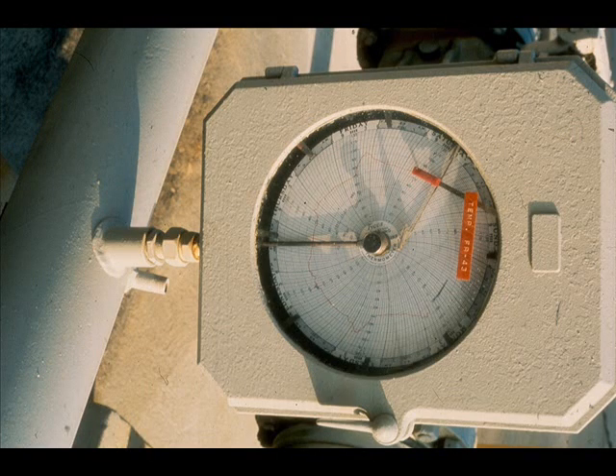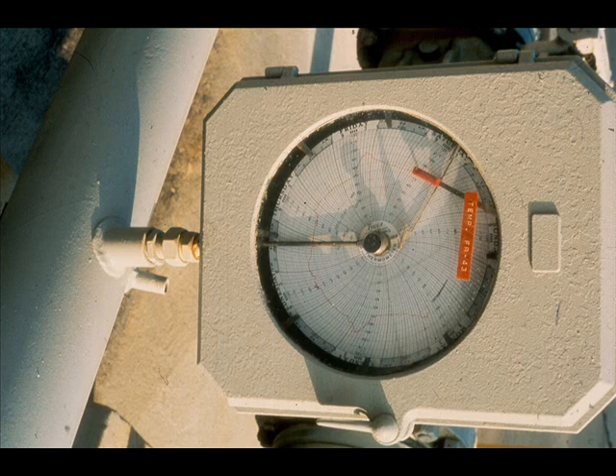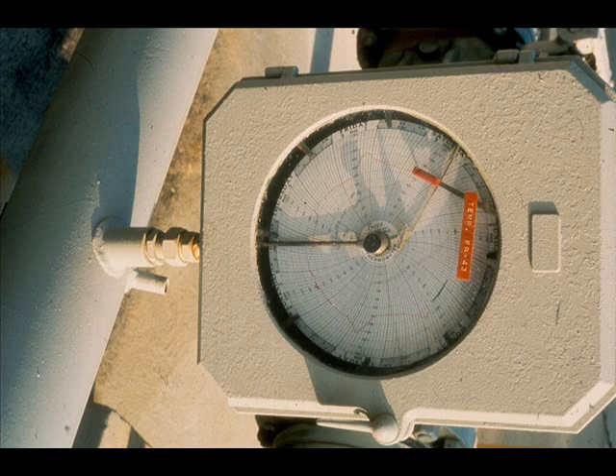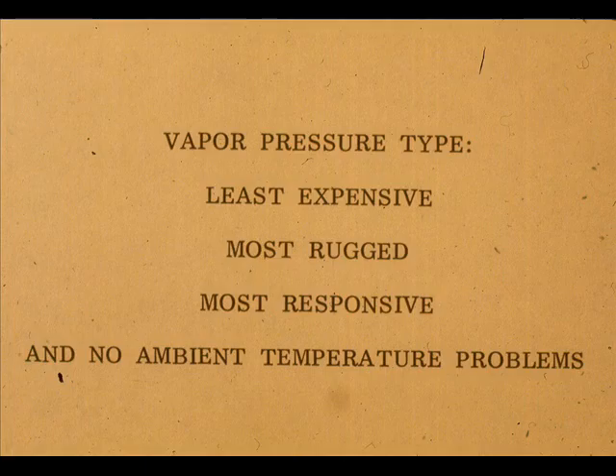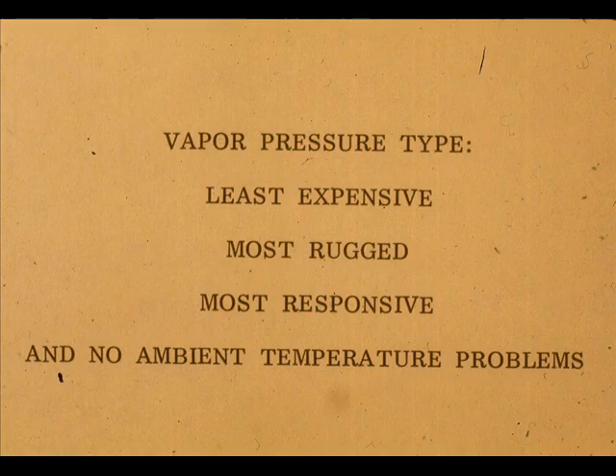If you should ever need to select a filled thermal system for a particular installation, consider the systems in this order. Your first choice should be the vapor pressure type. It is the least expensive, simplest, most rugged, most responsive, and is not affected by ambient temperature changes.